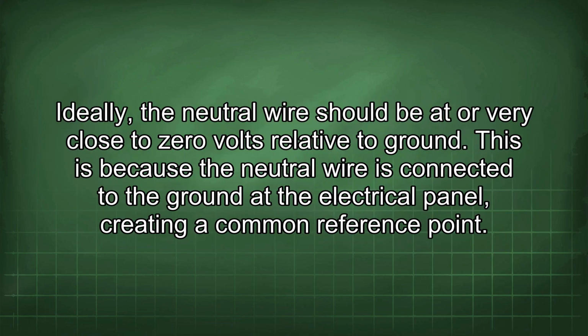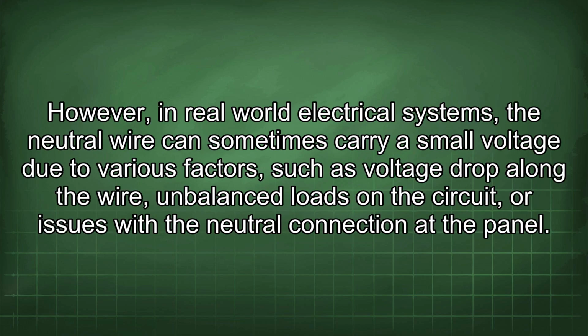Ideally, the neutral wire should be at or very close to 0 volts relative to ground. This is because the neutral wire is connected to the ground at the electrical panel, creating a common reference point. However, in real-world electrical systems, the neutral wire can sometimes carry a small voltage due to various factors such as voltage drop along the wire, unbalanced loads on the circuit, or issues with the neutral connection at the panel.